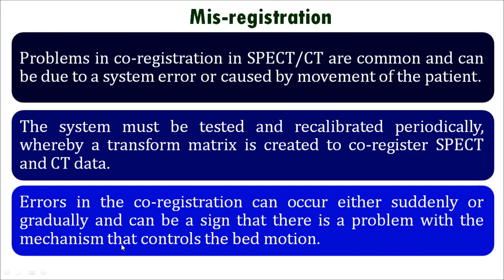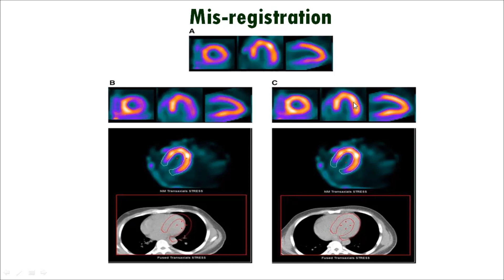This is the example where you can understand what will happen to the image quality if there is any misregistration. You see here the CT data is not perfectly aligned with the SPECT data, and because of that it will produce an attenuation correction artifact in your reconstructed images, and due to that we are getting a perfusion defect in this wall of the heart. After realigning the CT data with the SPECT data, this attenuation artifact, or perfusion defect, disappeared from the reconstructed image.